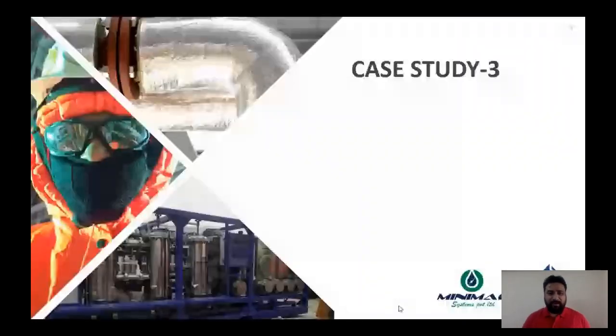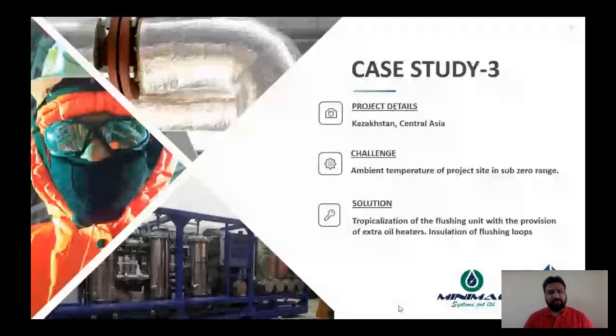The next case is from the Central Asian region, where temperatures were sub-zero. The entire flushing was happening in ambient conditions of less than 10 degrees centigrade. When you hire flushing systems from other countries, they may not be tropicalized for the environment you're working in. So the flushing skids normally need certain heating devices to raise the temperature of the oil, which temporarily lowers the viscosity and helps achieve better flushing efficiency for your lines.